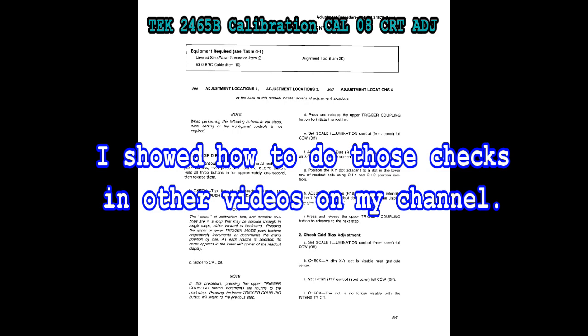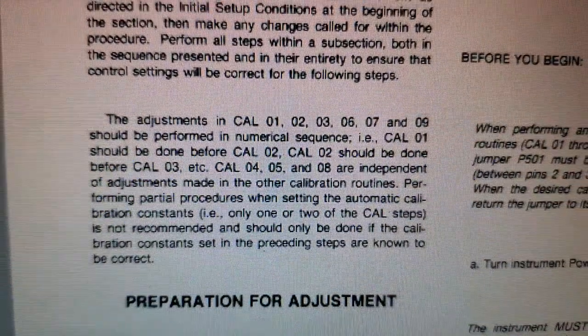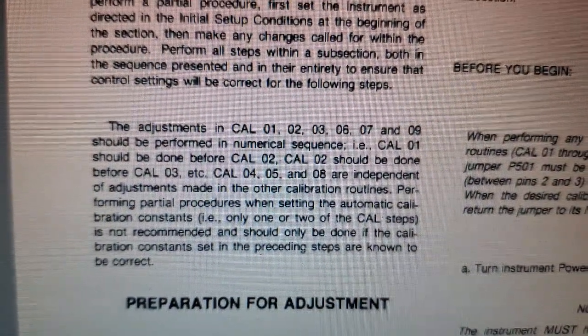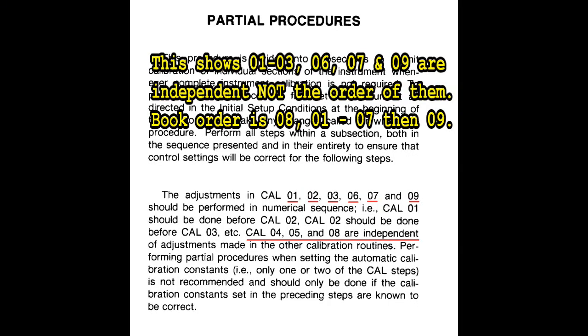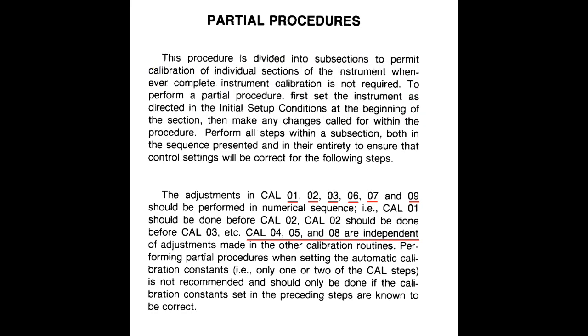One thing I want to point out is that Cal 8 is designed to be done per the manual before Cal 1 through Cal 7 and then Cal 9. Why they did it that way, I don't know. So if you're looking to do Cal 1 through Cal 7 and then do Cal 8 and then Cal 9, I don't recommend it. That's not what's in the book. It even talks about it a little bit in the book. So make sure that you do this procedure, the Cal 8, before you do the rest.